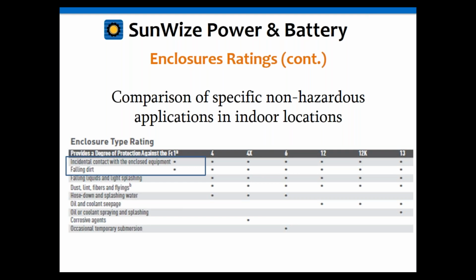This is just a little comparison with regards to the different NEMA types. In this one, they actually included NEMA 4 and 4X along with NEMA 1 and NEMA 12, mixing some of the outdoor and indoor together. Again, this is all non-hazardous—hazardous ratings are completely different, we're just focusing on non-hazardous at this point. The key here is NEMA 1 is for incidental contact, basically somebody sticking their hand or finger in an enclosure, and just falling debris and dirt—not something that could get splashed or sprayed into it. For that, you might want the NEMA 12 rating for indoor use.